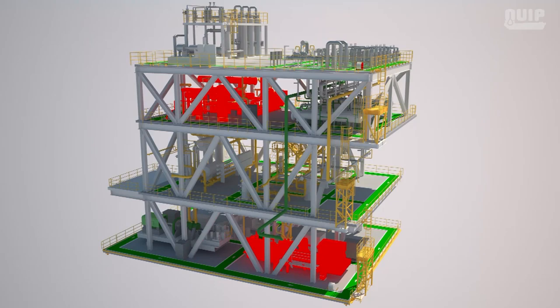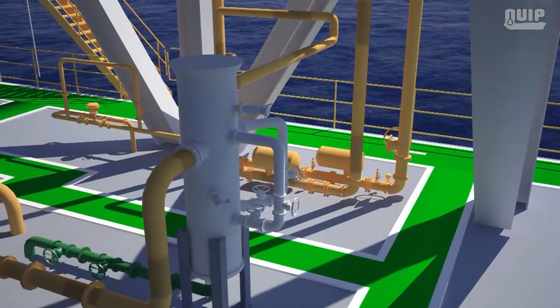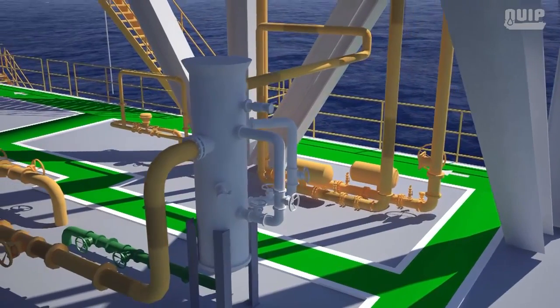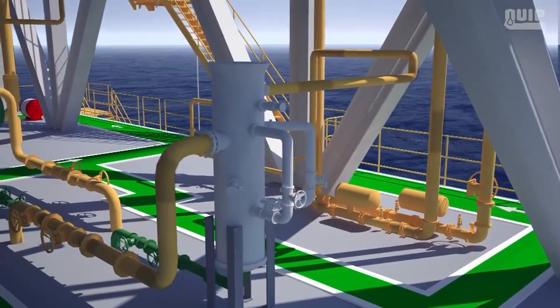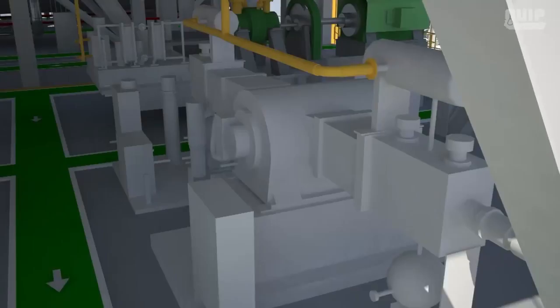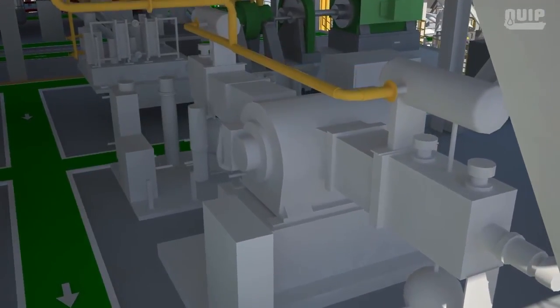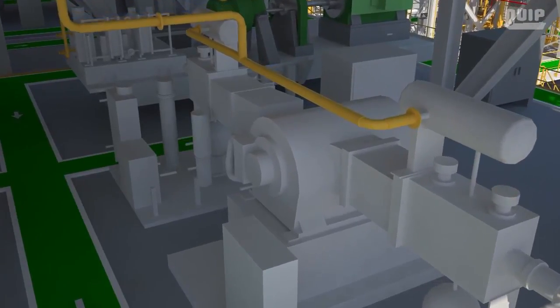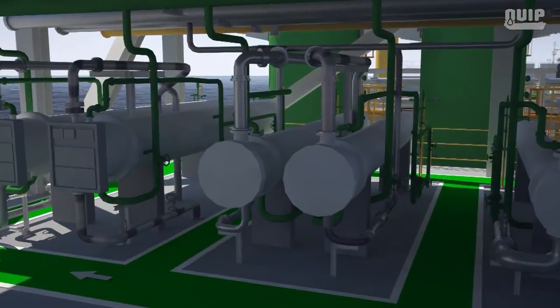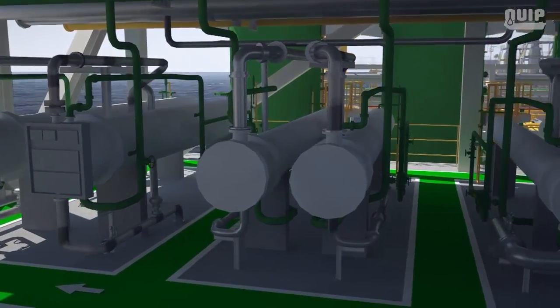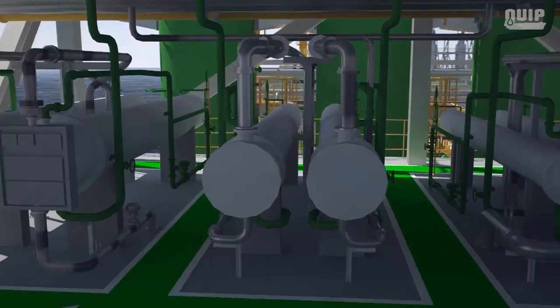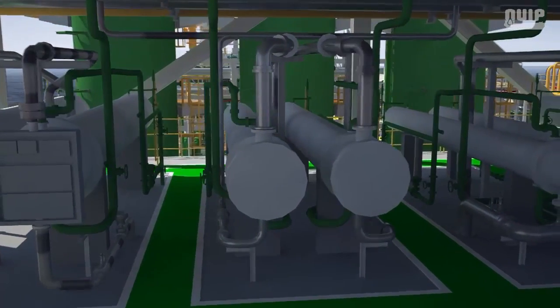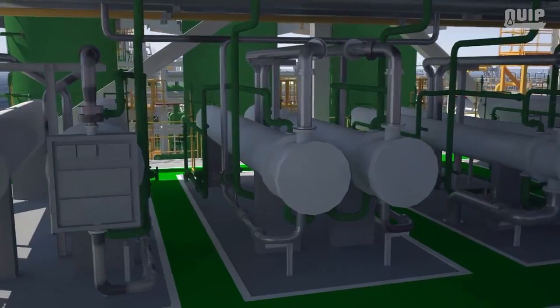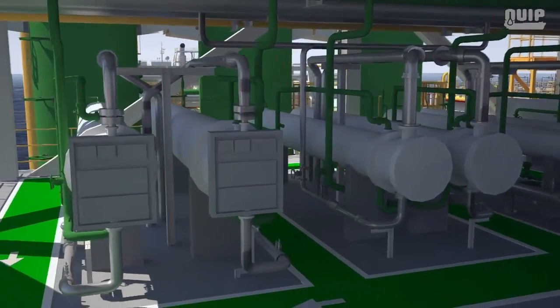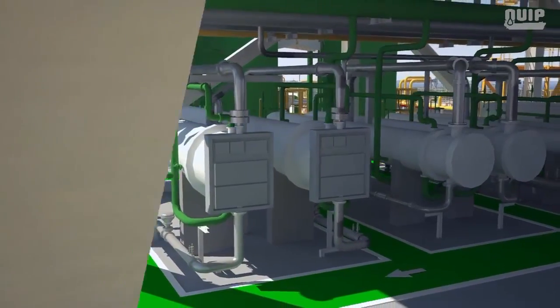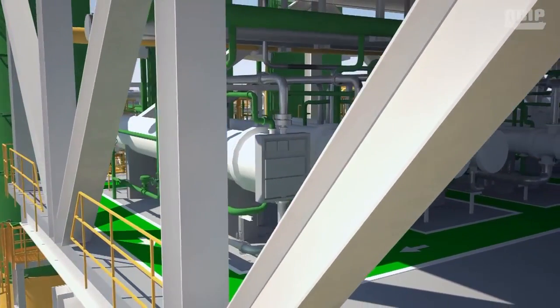In the third compression stage, the gas first goes to a scrubber to remove any droplets of liquid that might remain before entering the main compressor, where its pressure will increase from 80 bar gauge to 300 bar gauge. The pressurized gas is cooled in a cooler and then sent either to a gas reinjection well or a gas lift system. The portion of the gas sent to the fuel gas treatment system is cooled in a multi-stream heat exchanger, with its fluid being used to cool the products obtained in the low-temperature separation vessel.